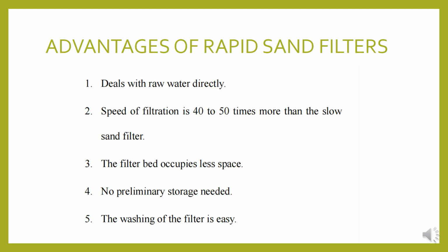Advantages of rapid sand filters: it deals with raw water directly. The speed of filtration is 40 to 50 times more than that of slow sand filters. The filter bed occupies less space, no preliminary storage is needed, and washing of the filter is easy.